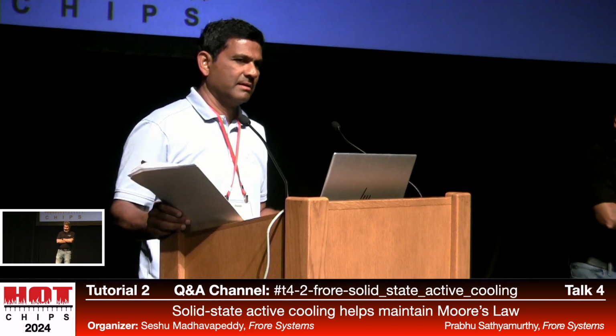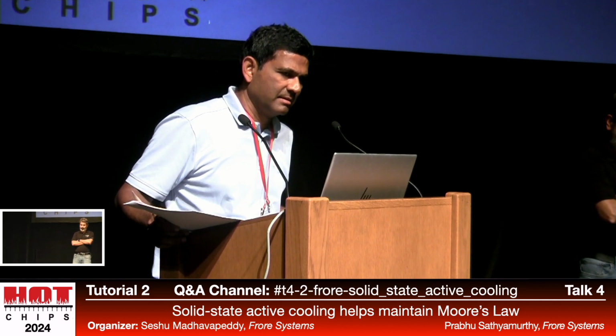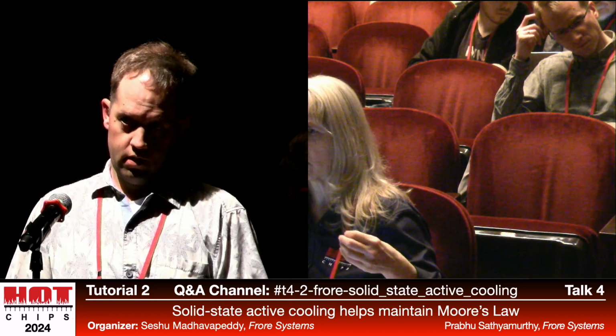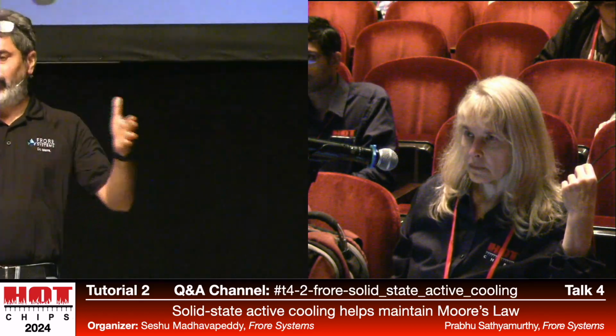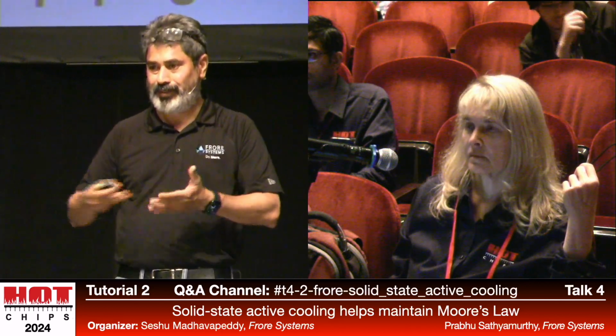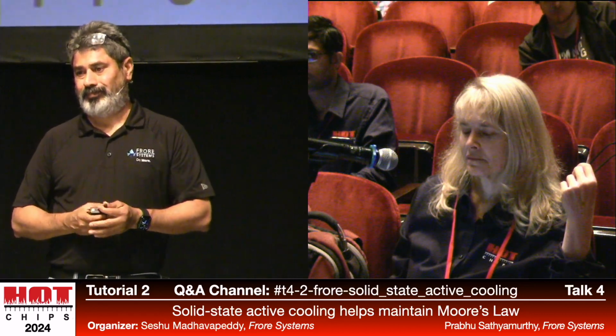Question from Ashwin Nanjapa at NVIDIA about the possibility of dust coming in through the jets, or if there's a filtration requirement for using this air jet. Good question. The same back pressure or static pressure head I discussed would allow you to put a system dust guard, even a MERV 14 grade dust guard, in the system with no loss in performance, so that's certainly possible at the system level to protect it from incoming dust. For our purpose, the system is also self-cleaning as it runs, so reliability and life aren't affected by dust because we clean periodically, operationally speaking.